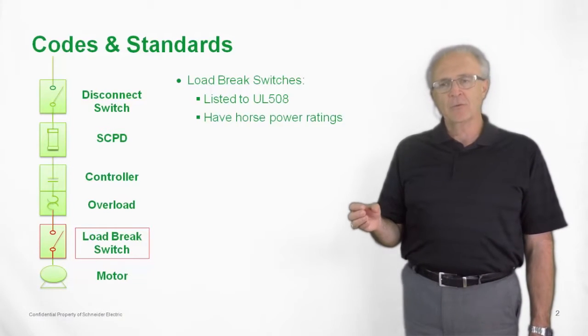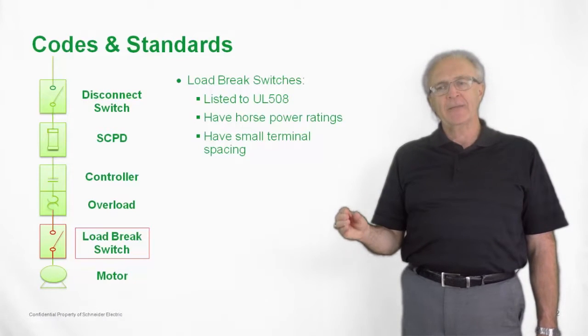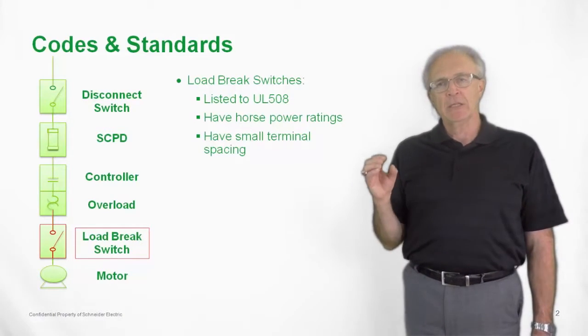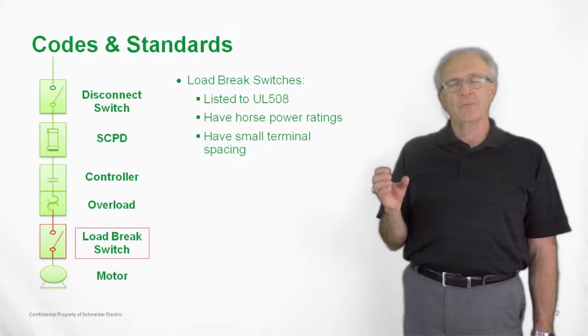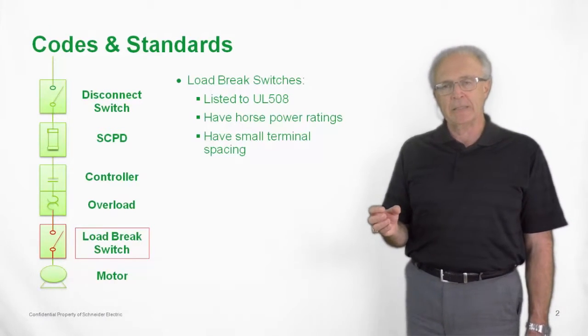They do have horsepower ratings, and they do have a smaller spacing — that is one of the main criteria why it is a UL508 switch. The UL98 switch, which would be positioned as the disconnect switch, is a much larger switch. It can handle the voltages that come in and any type of interrupting circuit that it may need to clear.